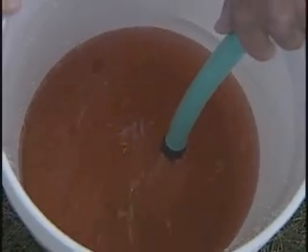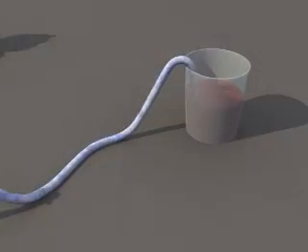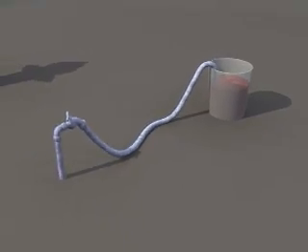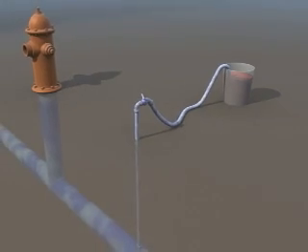This is a simple cross-connection possibility. Non-potable liquid in the bucket meets the potable water system in the hose. Now, let's also assume that Fred has opened his spigot and the water starts to fill the bucket. After a few seconds, the fire department begins to fight the fire and pulls a tremendous amount of water out of the water system. This might create a backflow in the system, and let's use our animation to show how this might all work. Potentially, the water in this hose can start to be sucked backwards.